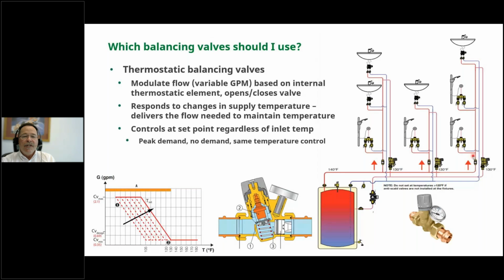So you just install these, an adjustable one, you just set the knob to 120 or 125 or 115 or whatever you want, and you're done. Great for retrofit. Why? If you go into a building and you don't really know where all that piping is behind the walls, you don't know the heat loss of the system, you don't know the GPM, it doesn't matter. Just put these in, and as long as that riser or that secondary circuit has some hot water, the valve will try and maintain the temperature in that section of the piping.